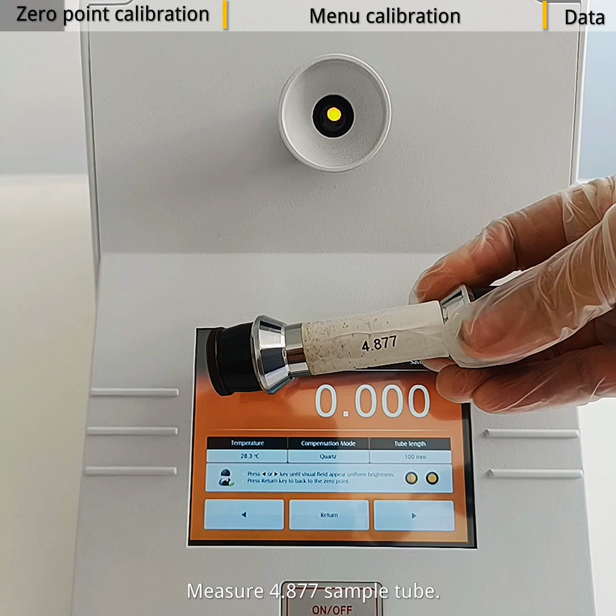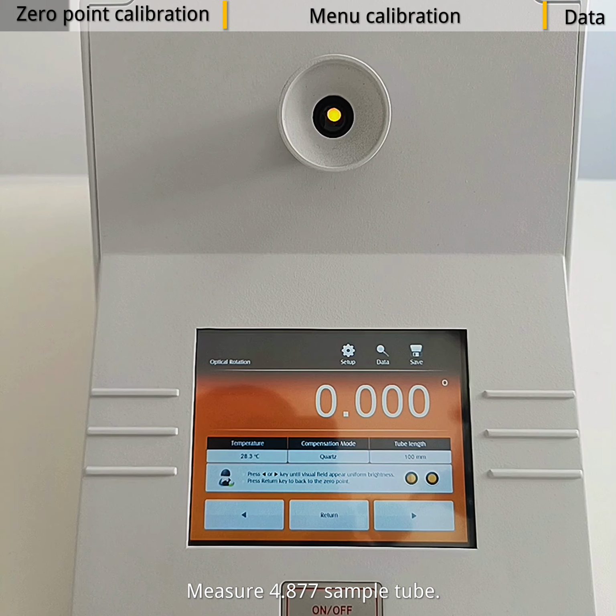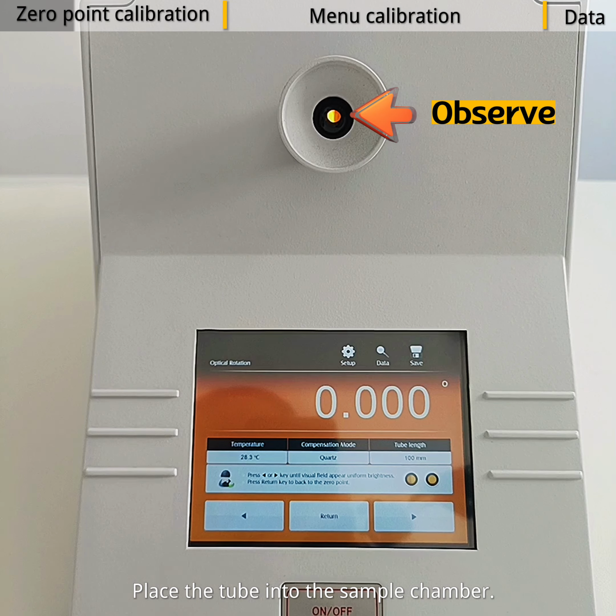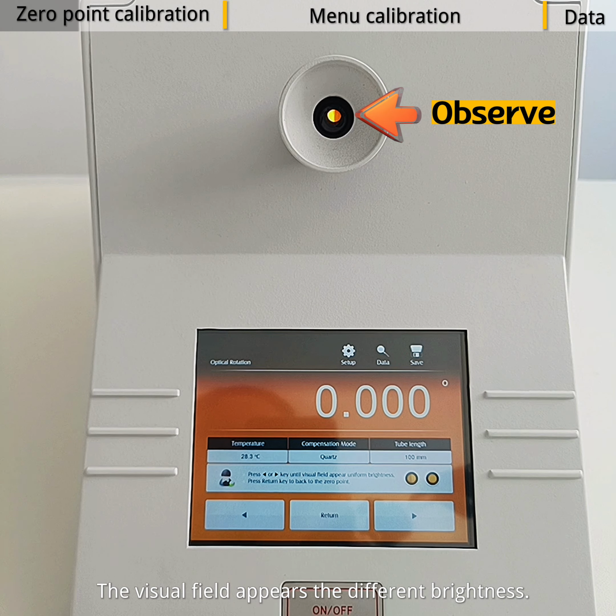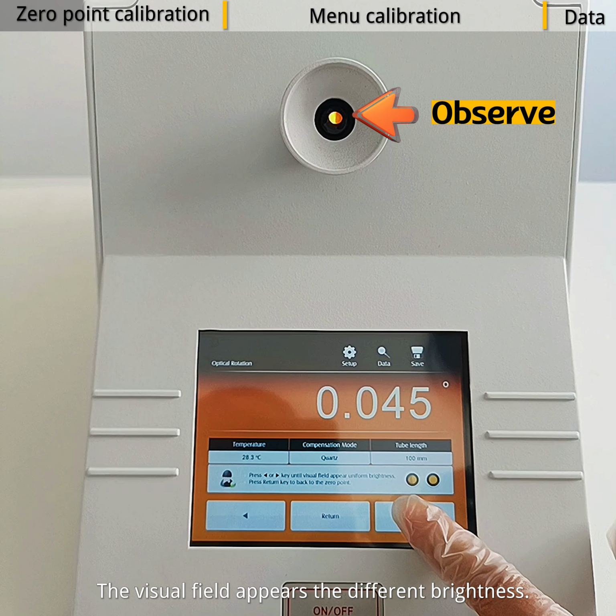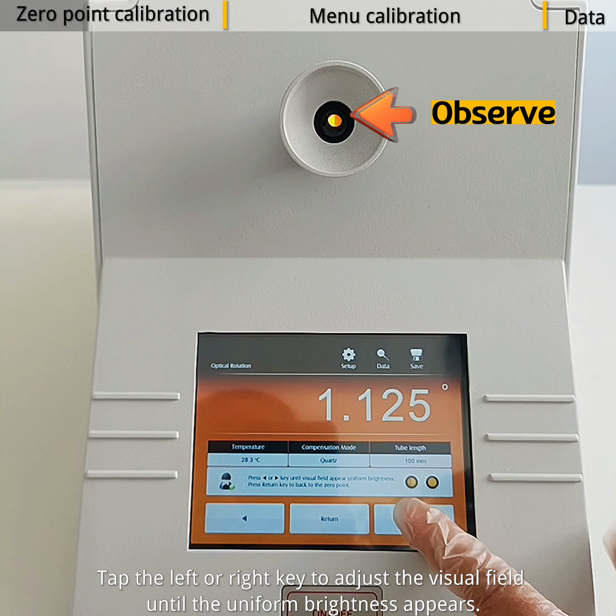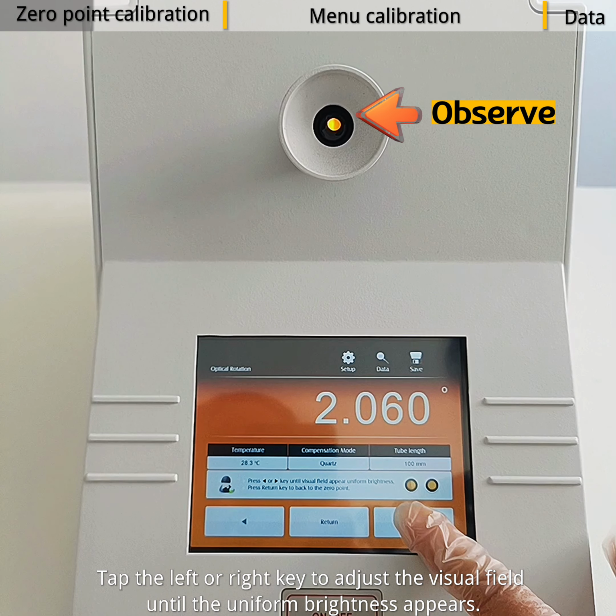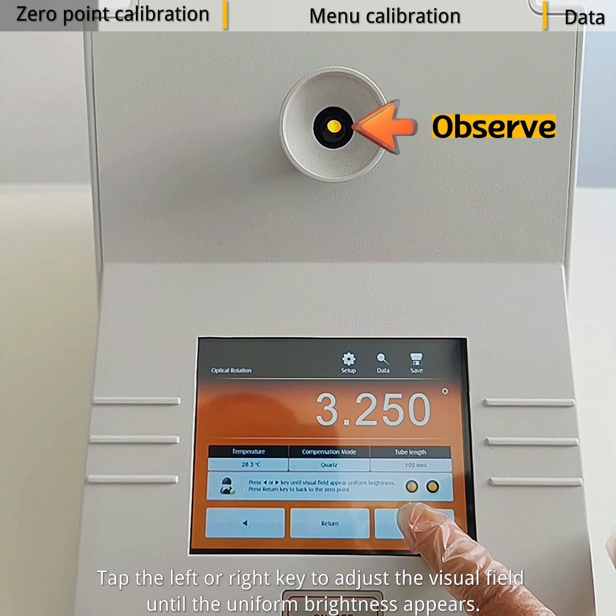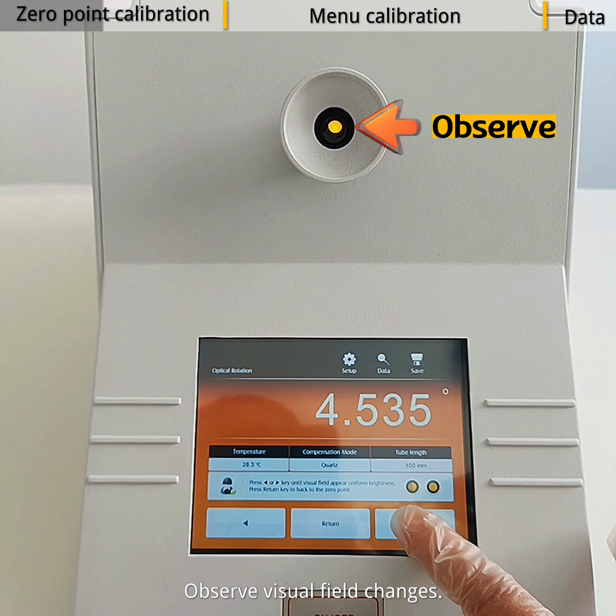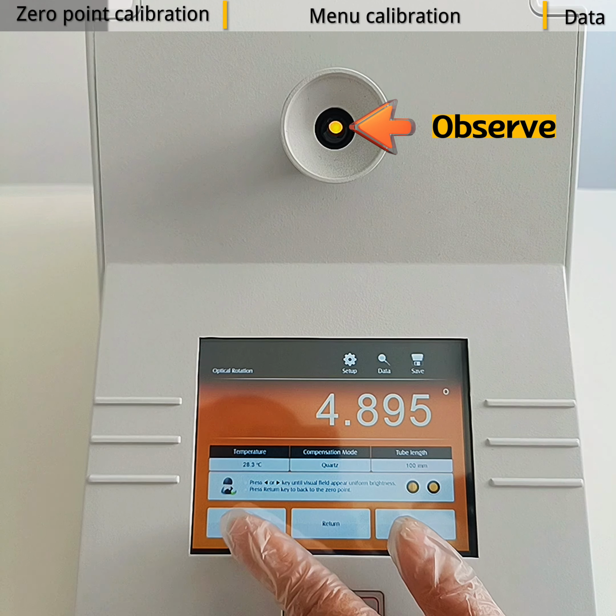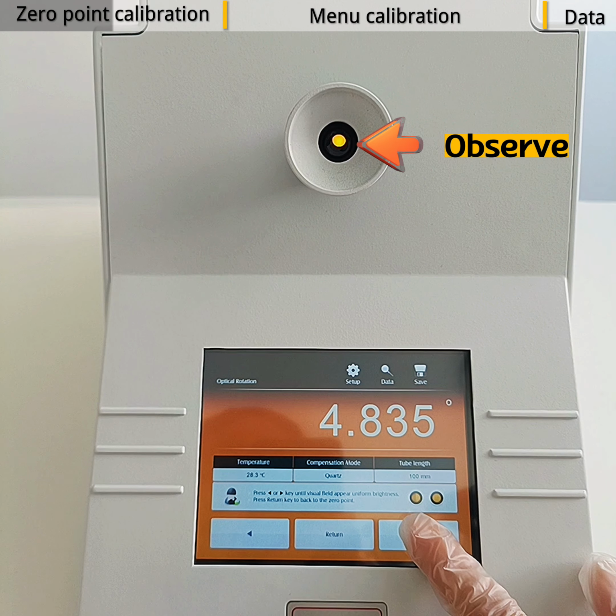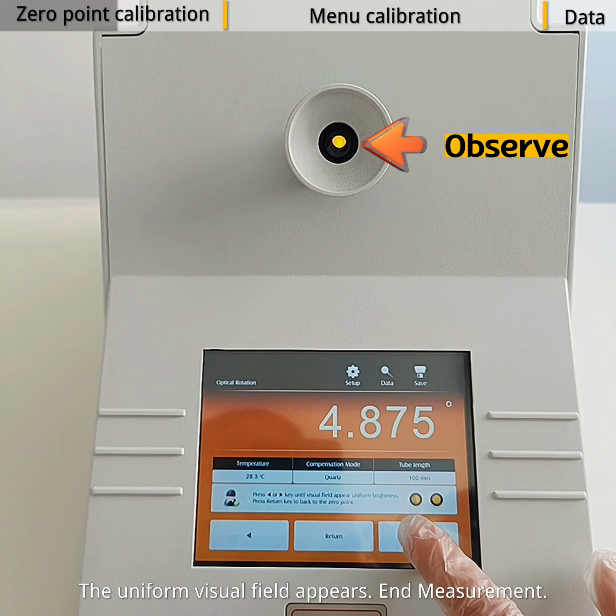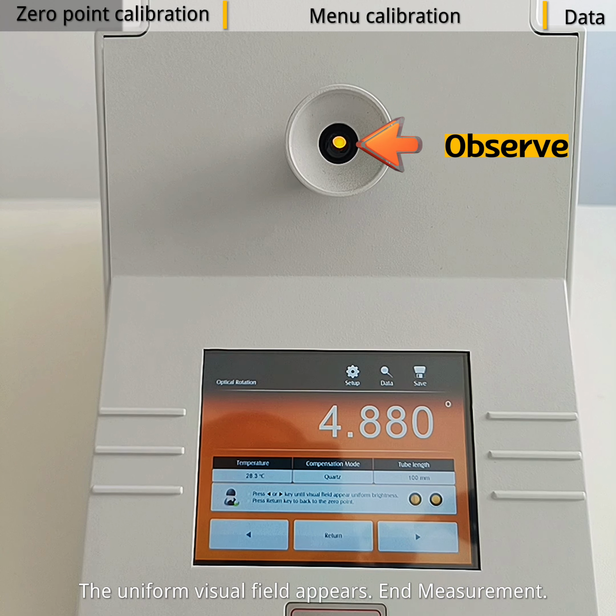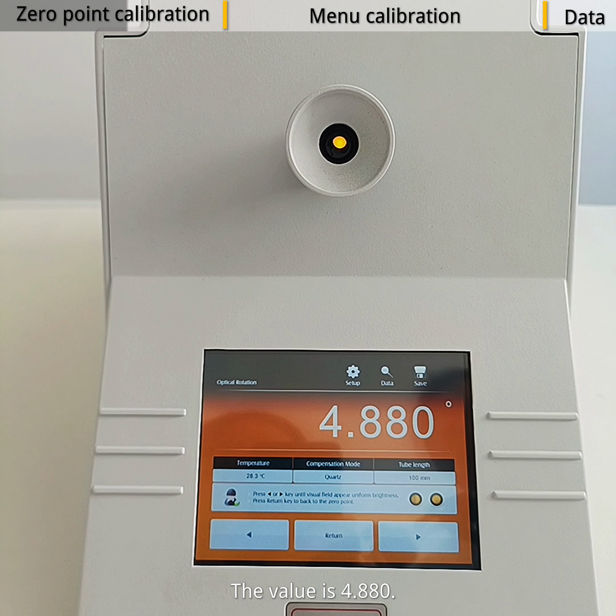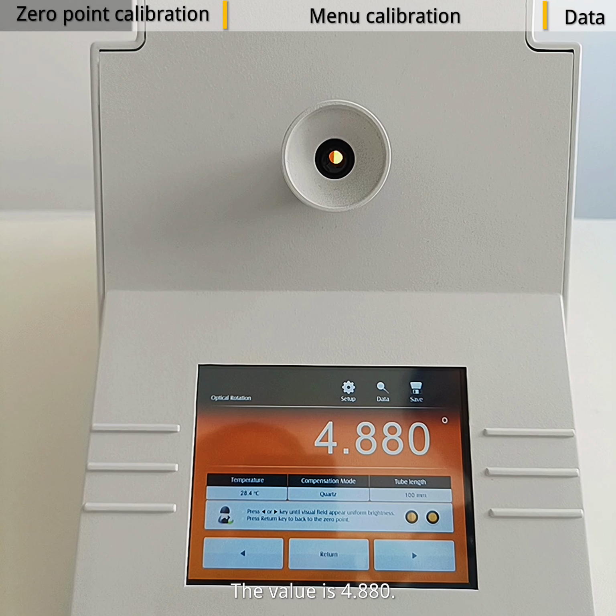Measure 4.877 sample tube. Place the tube into the sample chamber. The visual field appears the different brightness. Tap the left or right key to adjust the visual field until the uniform brightness appears. Observe visual field changes. The uniform visual field appears. End Measurement. The value is 4.880.